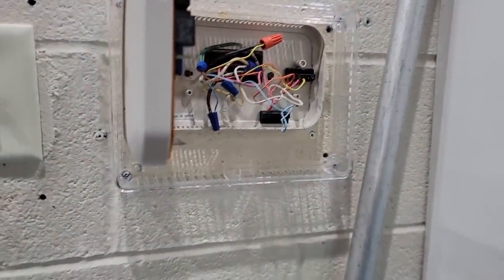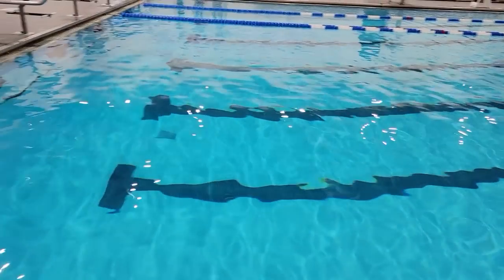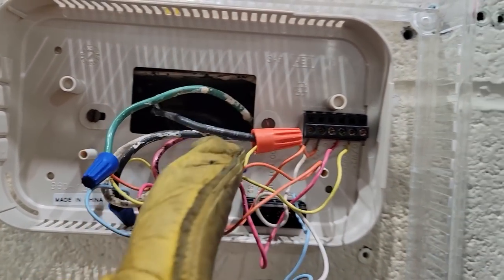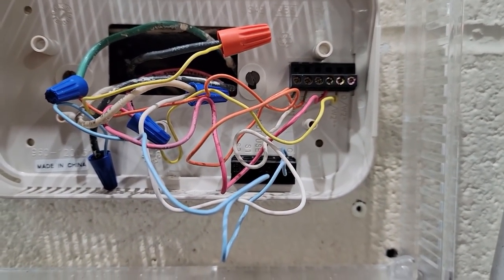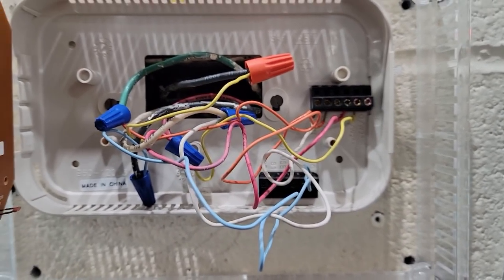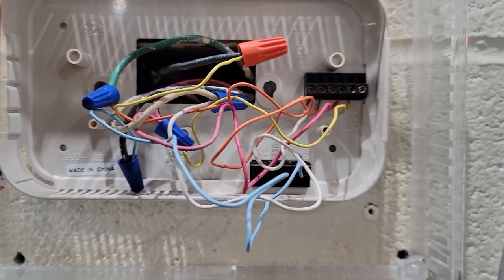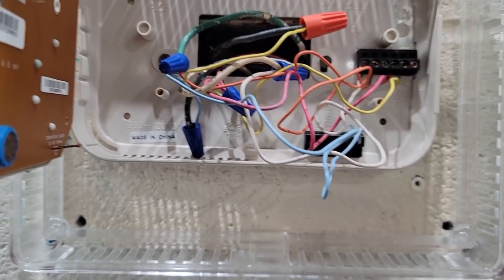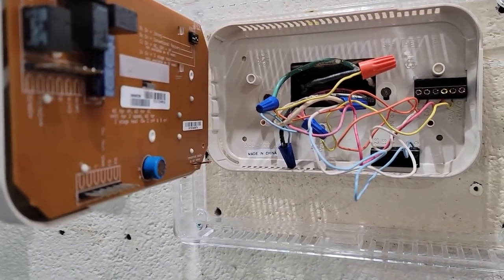Hopefully we don't get a copyright strike from the radio. The area it takes care of is a pool area, so it's definitely high humidity in here. We're tracing these down. What doesn't make sense is that it actually has Y hooked up, but there's no cooling up there. They don't even have mechanical dampers. It probably was a totally different system and some chuck in the truck came in and underbid people — this is what ends up happening.